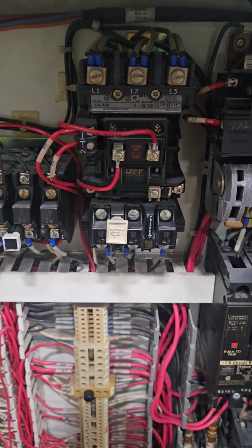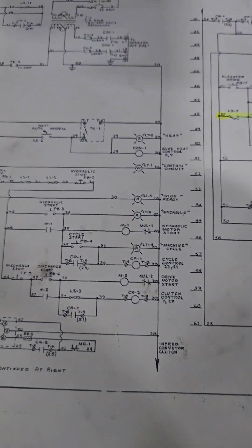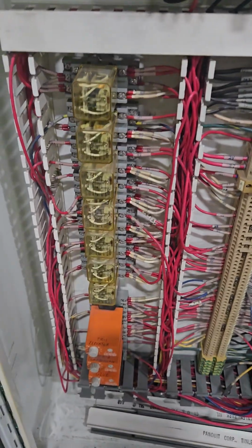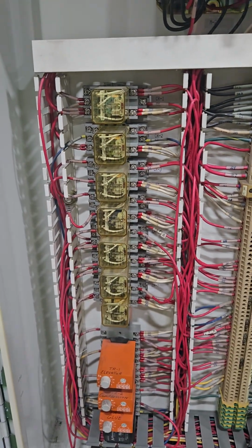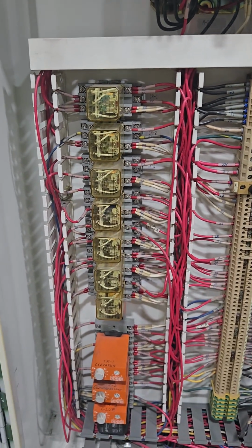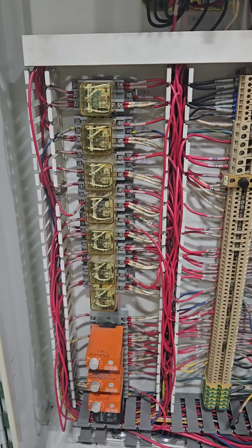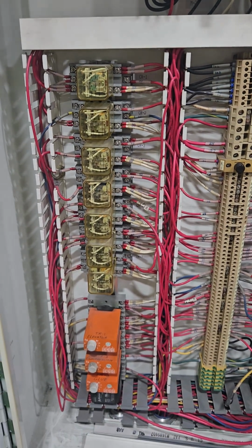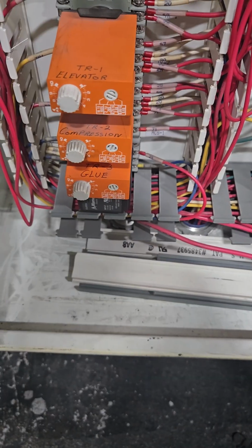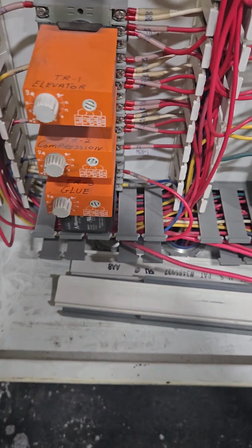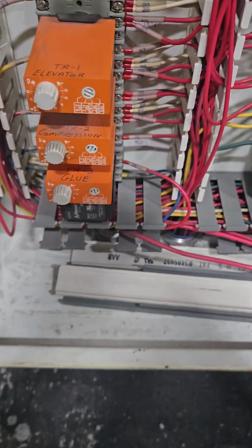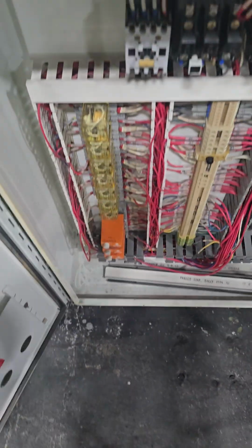This right here is a motor starter, and we'll look at the diagram and find out where it is too. And as you can see, all these relays here are interlocked. The reason why they are interlocked is so that some equipment cannot be energized both ways, such as forward and reverse, or up and down, at the same time. And here are some timing relays, and there is also a clutch and a brake relay down here. I'll show you some symbols and what they mean on the diagram.